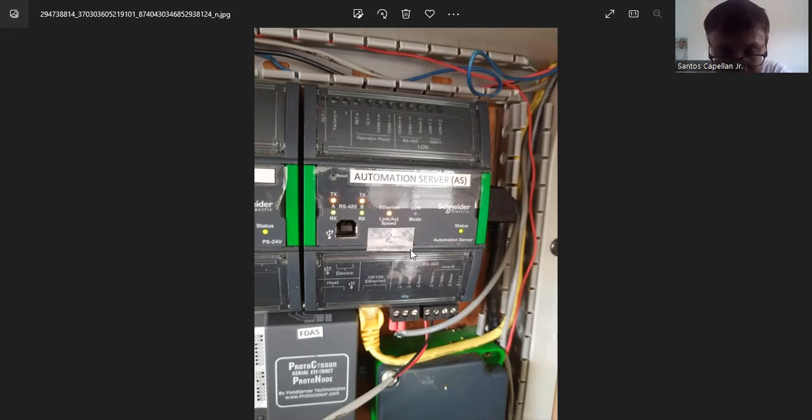Before, in my previous tutorial, I configured this communication port for Modbus. But since I need to integrate this VAV box, I deleted that interface, and again I'm using the BACnet interface. Now, in the BACnet interface, you can create several BACnet MSTP networks. So, I have a BACnet MSTP network number one.